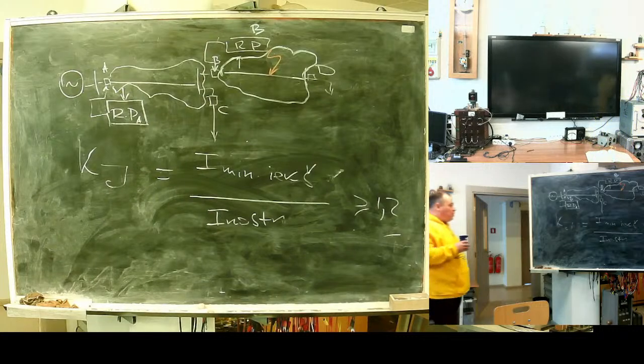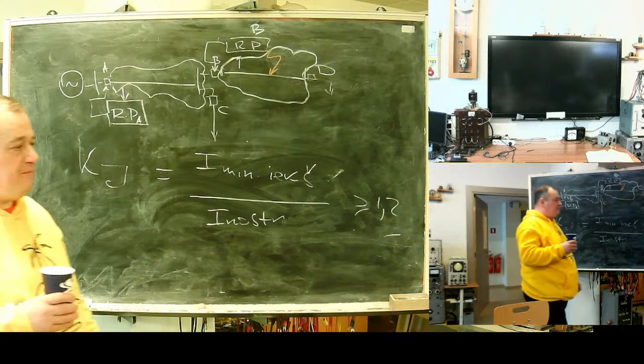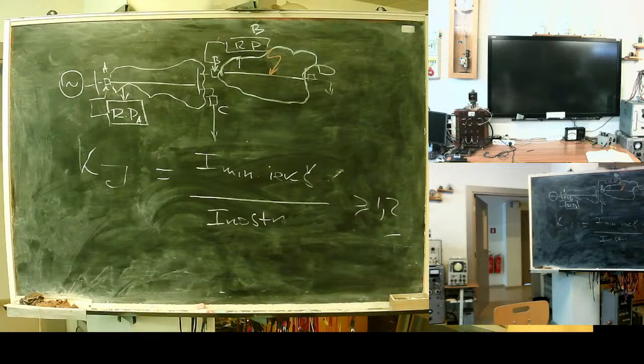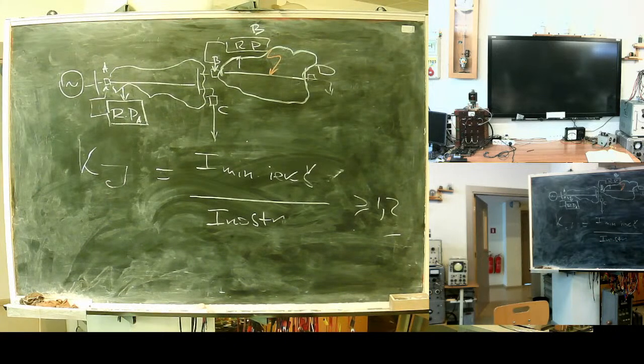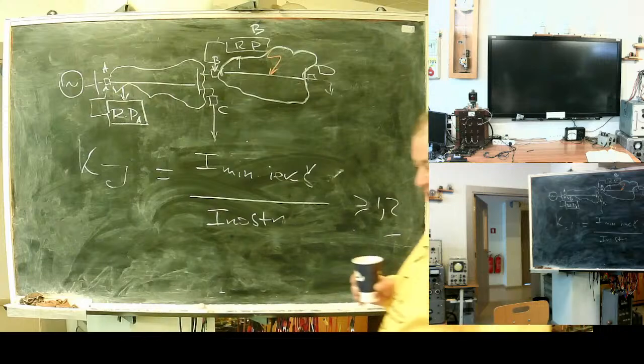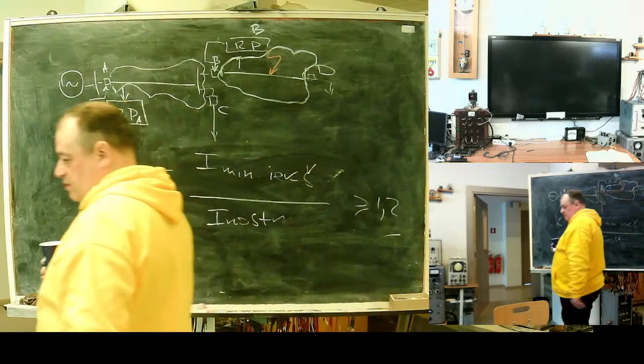So, the problem is that in your design of protection, you need to fulfill both criteria. You should ensure your device is sensitive and your device is selective. And that's not all. There are two more points.